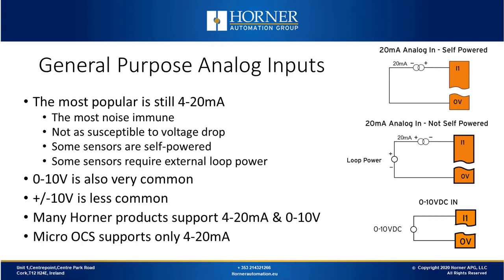From a general purpose standpoint, 4-20mA is still the most popular. It's the most noise immune because current is less susceptible to noise than voltages, and it's not as susceptible to voltage drop either. Some 4-20mA transmitters or sensors are self-powered; others require external loop power — we support both with our products. 0-10V is also very common, and plus or minus 10V is also supported in some cases. Most Horner products support both general purpose signals, 4-20 and 0-10V. The Micro OCS series supports only 4-20mA as it's the most popular.